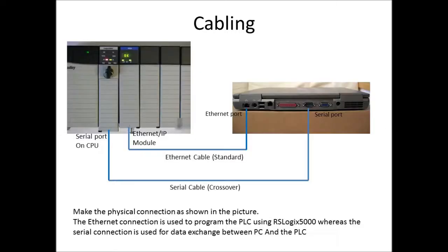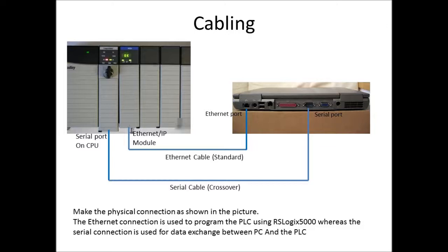Shown in this figure is the required physical interconnection between the PLC modules and the PC. The CPU module has an inbuilt serial port which is normally used for programming. However, since we intend to use that port for sending and receiving ASCII data, we need another communication module, namely an Ethernet IP, so that we can go online to the PLC and do the programming.